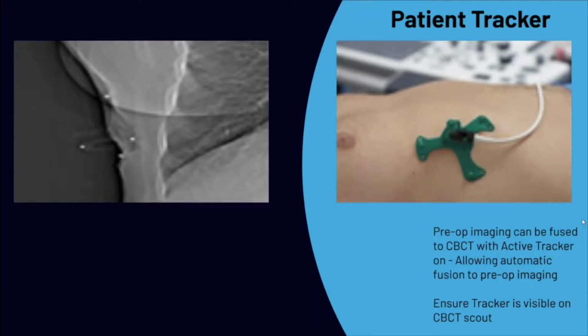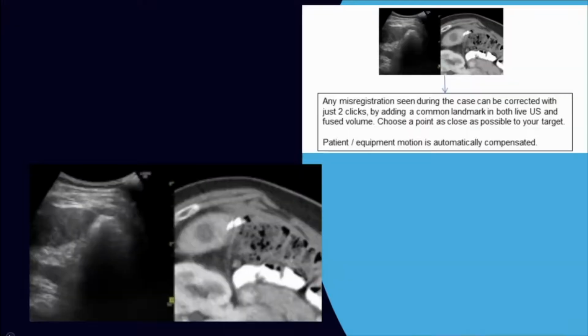So we've created some guiding cannulas that will accept our ablation probes that are of exact lengths for the guiding probe, and then you can place that in, exactly localize the tip of your needle and where the tip of it will go. And when your probe goes in, it goes in 2 centimeters beyond and allows a 2 centimeter burn, or it can go in 4 centimeters beyond and allow a 4 centimeter burn. One of the things you want to make sure is that you see the tracker on the cone beam CT. This one was to see all 4 points. The newer systems really only require that you see these 3.